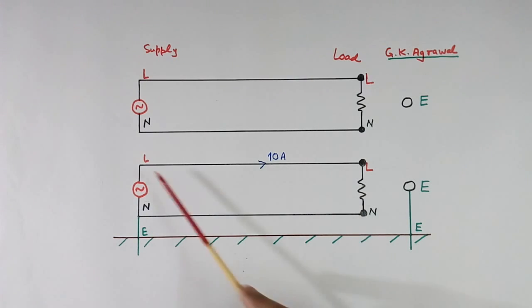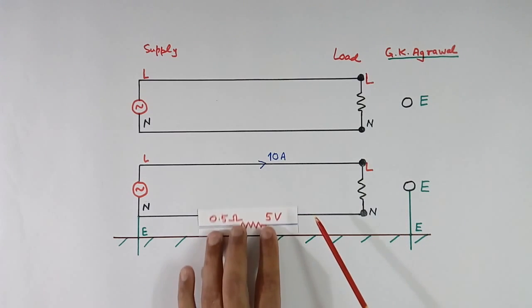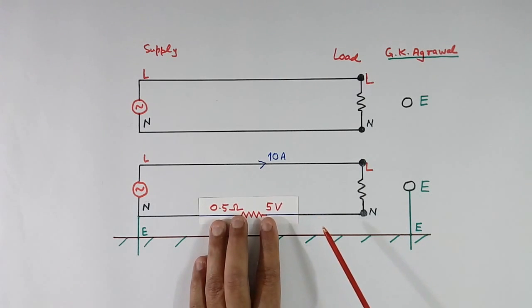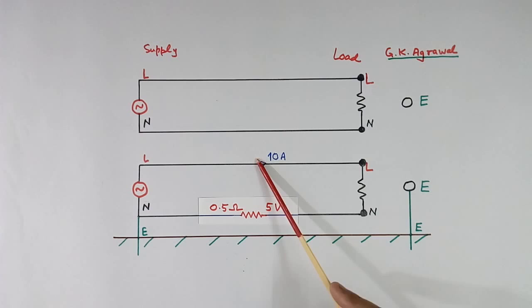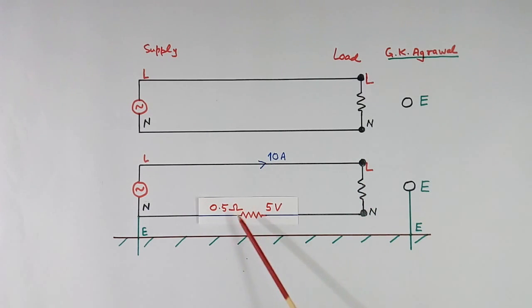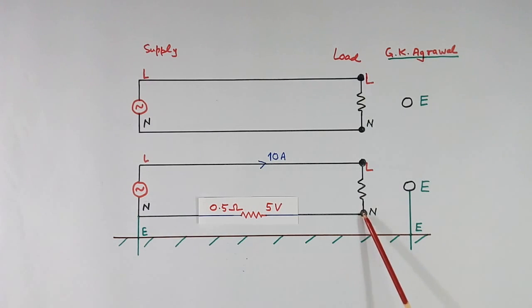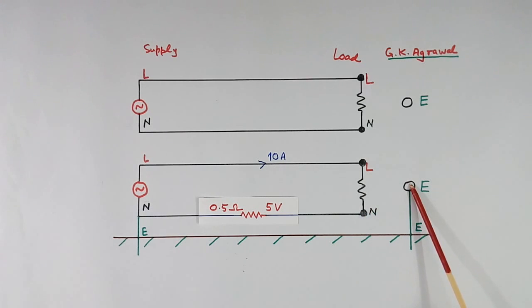These wires are very long and will have some resistance. Suppose this resistance is 0.5 ohm and 10 ampere current is flowing — so here a 5 volt drop will be there. So if this point is 0 volt, the other point will not be 0 volt — it will be 5 volt. So the voltage of neutral and earth will not be the same.